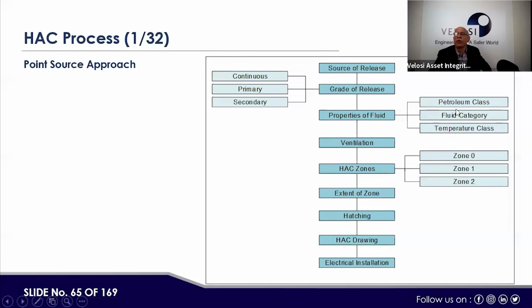Then properties of the fluid, for example petroleum class, fluid category, temperature class. Then ventilation, which is applicable depending on whether the plant is in a closed building or in the open. Then HAC zones, zone 0, zone 1 or zone 2, extent of the zone, then hatching, the HAC drawing, and then electrical or instrumentation equipment installation. So these are the practical steps for HAC drawing preparation.